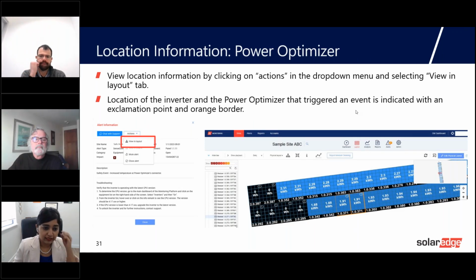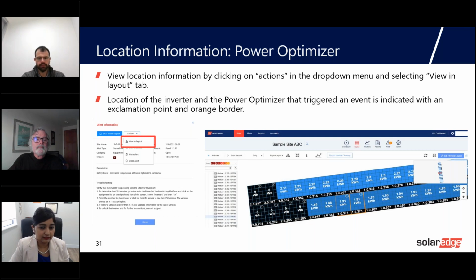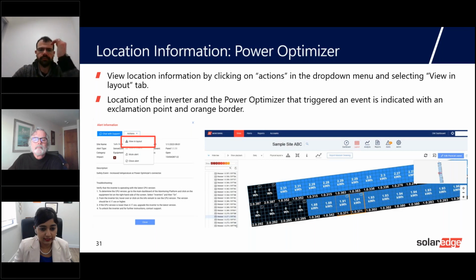So if you look in the site level alert pop-up, you can also view location information by clicking on actions in the drop-down menu and selecting the view in layout tab. So this is where you can pinpoint where the fault exactly occurred, and provided that the site was previously mapped, the location of the inverter and the power optimizer that triggered this event is indicated with an exclamation point and an orange border. I know that the screenshot is probably too small, but we will send you a copy of this deck so you can take a closer look at the screenshots there.